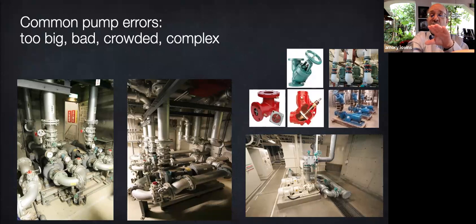So smooth, straight flow and efficient operation require at least 5 diameters of clear pipe run on the inlet side, 8 is ideal, and at least 3 on the outlet side, 5 is ideal. The pipe should be as big as the pump connection. If you need to neck down a pipe size, do it far from the pump so the turbulence can dissipate before it gets into the pump. These are just basic good practice principles, but often ignored. Unnecessary fittings, especially if they're near the pump, also add friction and turbulence, such as the ubiquitous end suction diffuser. It's an undesirable elbow and fitting size reducer combined with straightening vanes to reduce swirl caused mainly by pipes that are too short or crooked coming into the pump.